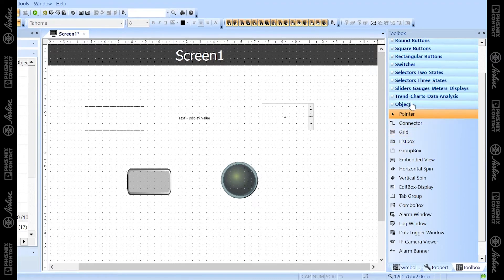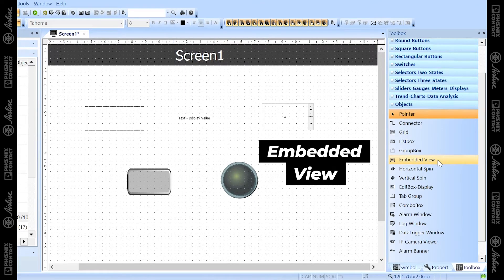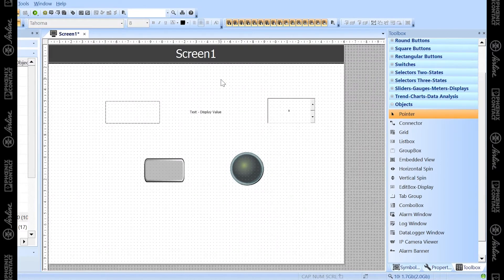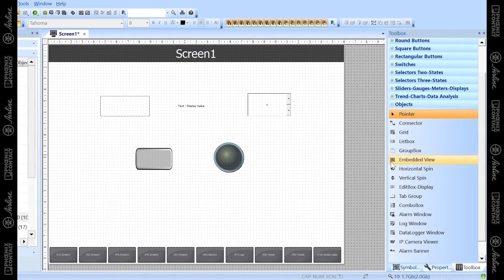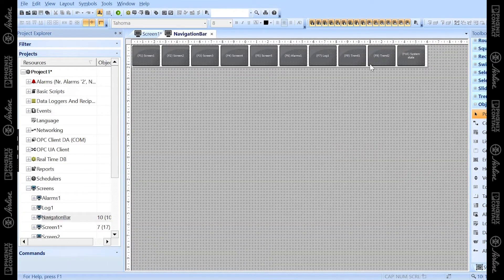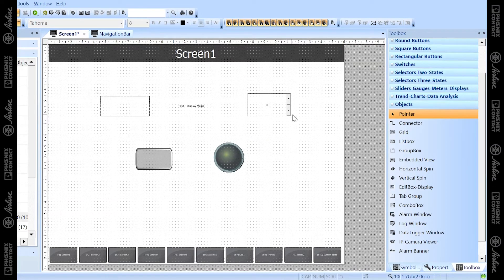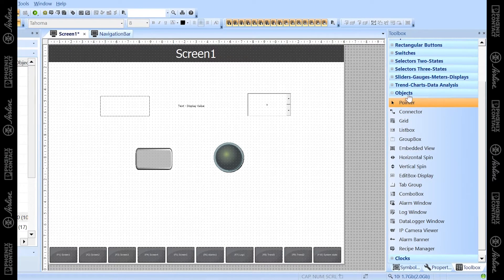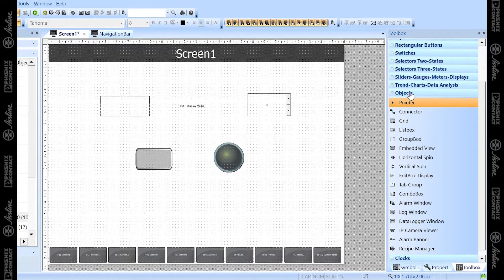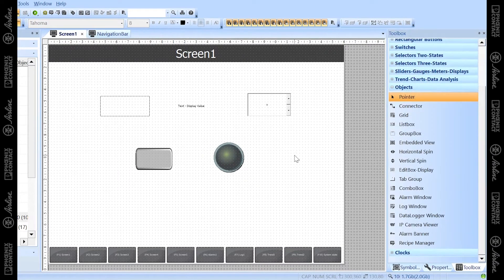Also under objects there are a lot more shapes and objects you can add. Some you might use are the embedded view, which actually embeds one screen into another — for example, the navigation bar on screen one is technically an embedded view of the navigation screen. There's also the edit box, which allows users to input values while the HMI is running. Other higher-tech objects we'll cover in later videos include alarming, logging, and even an IP camera viewer where you can view an IP camera right on the screen.